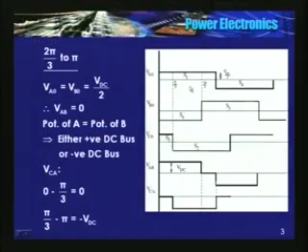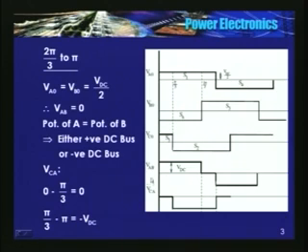Va0, Vb0, Vc0 are all square waves of Vdc/2, because the voltage is drawn with respect to the centre point of the DC link. Whereas the magnitude of line-to-line voltage Vab, Vca, or Vbc is the full DC link voltage. The magnitude of the line-to-line voltage equals the DC link voltage, but in each half cycle the magnitude is Vdc for only 120 degrees; for the remaining 60 degrees it is zero.